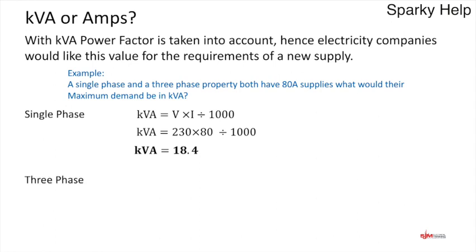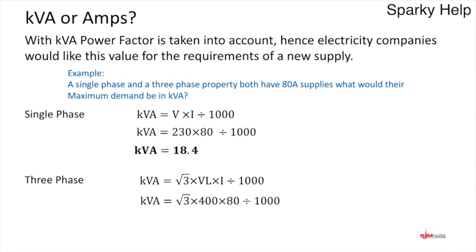For a three-phase installation, the formula is: KVA = √3 × VL × I ÷ 1000. Root three is 1.732, VL is the line voltage of 400 volts, times the current. So: √3 × 400 × 80 ÷ 1000 = 55.425 KVA. So for single-phase or three-phase, those would be the maximum KVA values for an 80 amp supply.